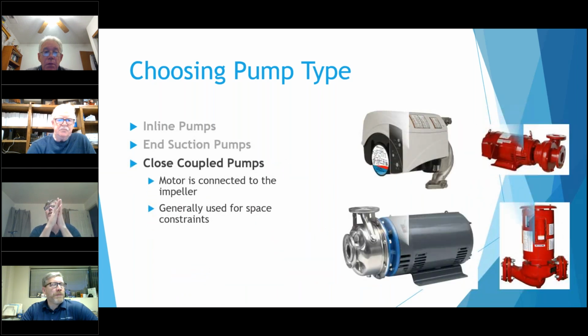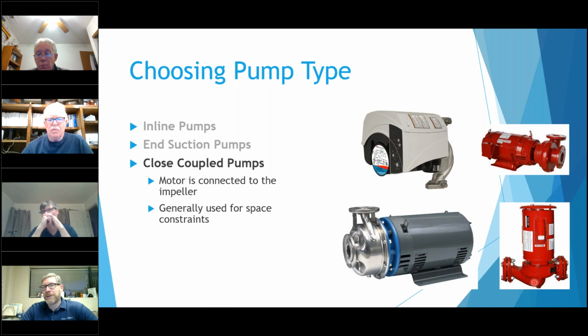But another type is close coupled. As you can see, there's no bearing assembly or anything like that. The impeller is connected directly onto the motor. A lot of times these are used really just for space saving constraints. I think they're a little bit harder to work on, because not only do you have the motor there, but you have the impeller hanging off of it. You've got a motor bracket. And on some of these pumps, where this motor bracket becomes pretty darn large, and this wheel becomes 9.5 inches, it takes a lot of energy, maybe even a crane, to pull them out to repair them. So it could be a little bit more difficult to do.